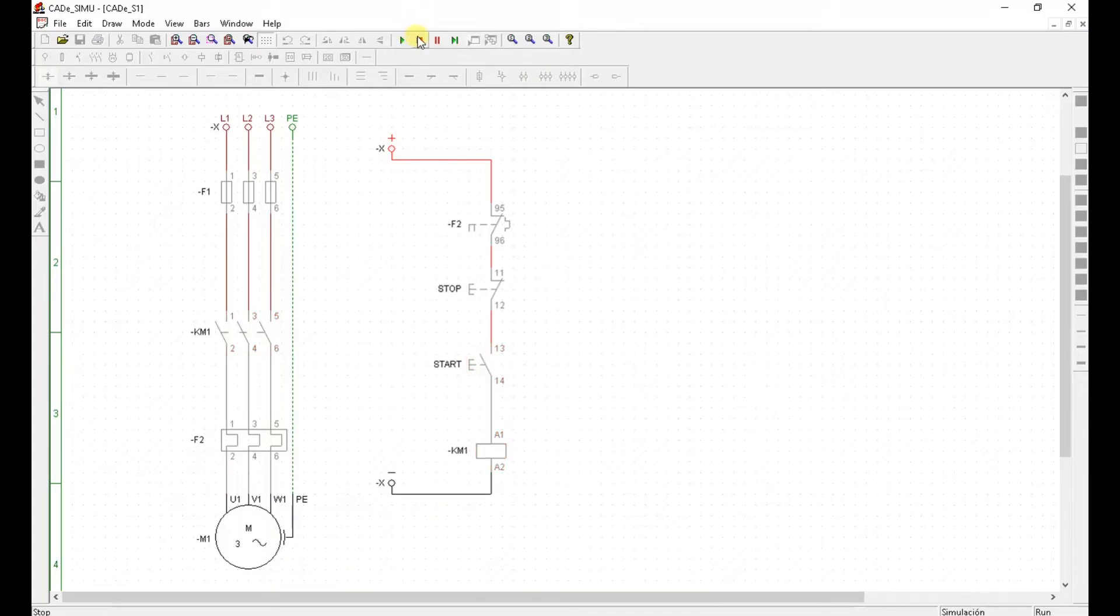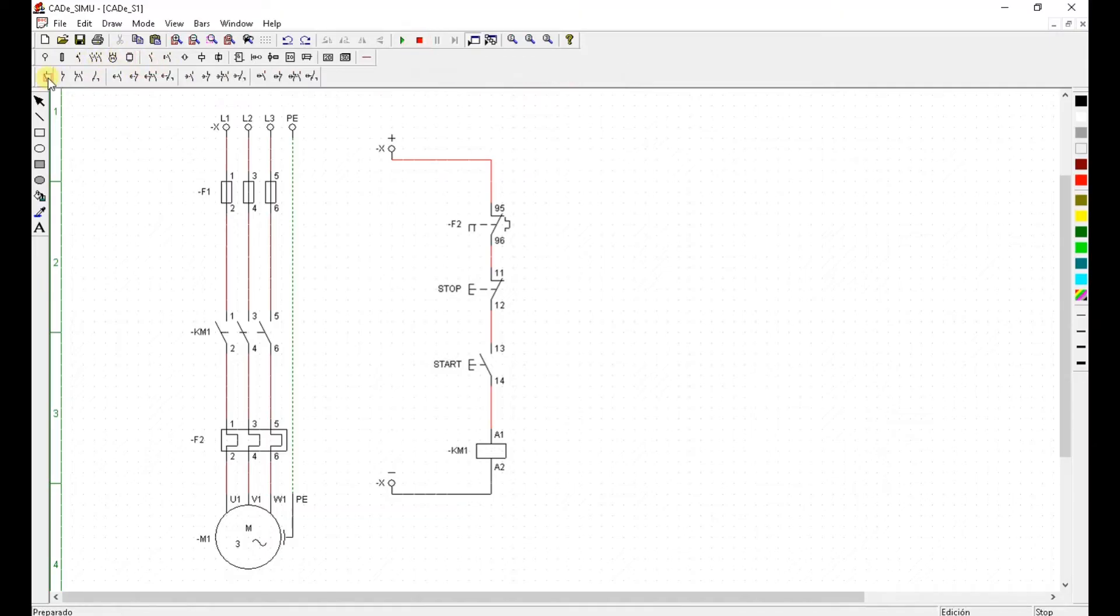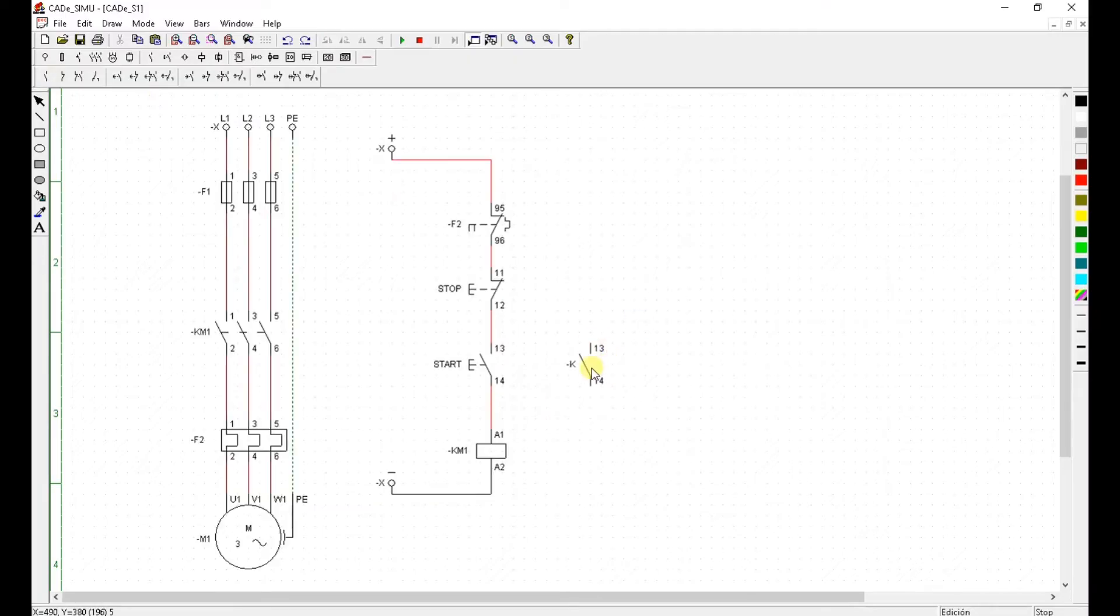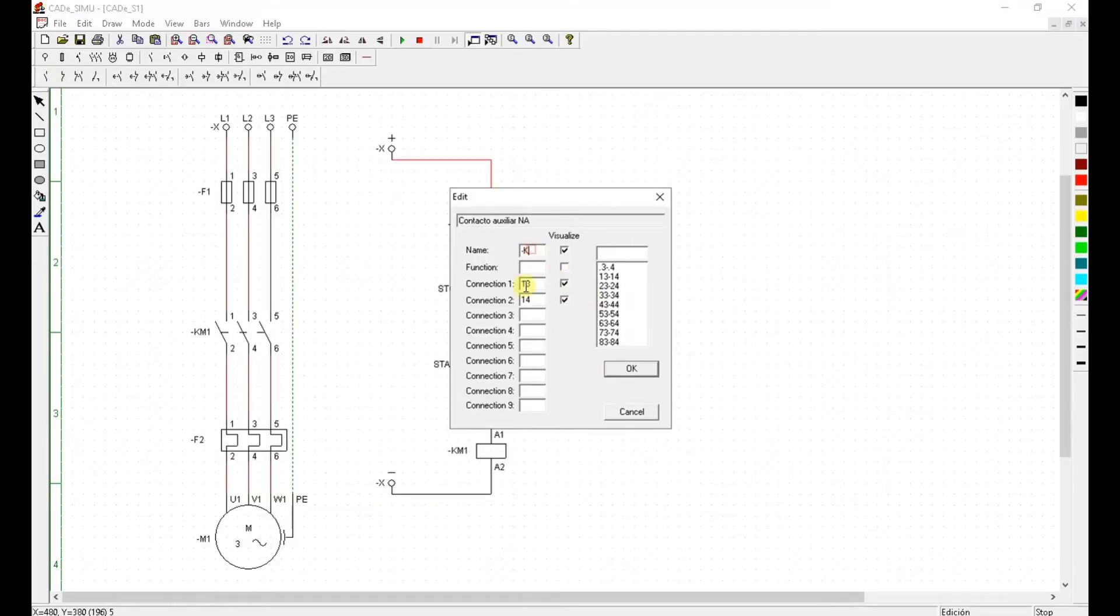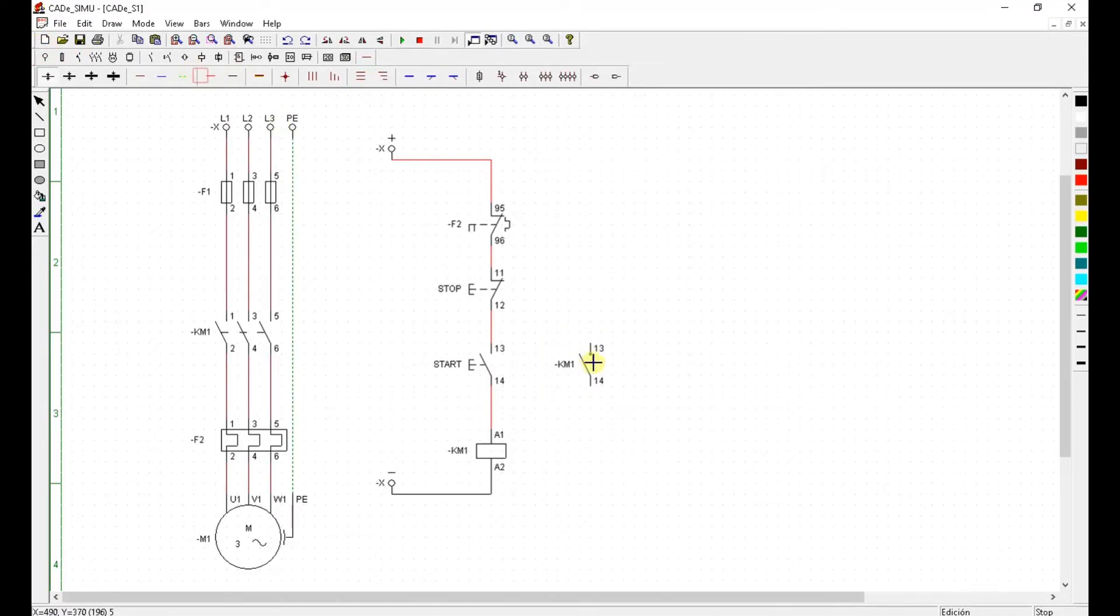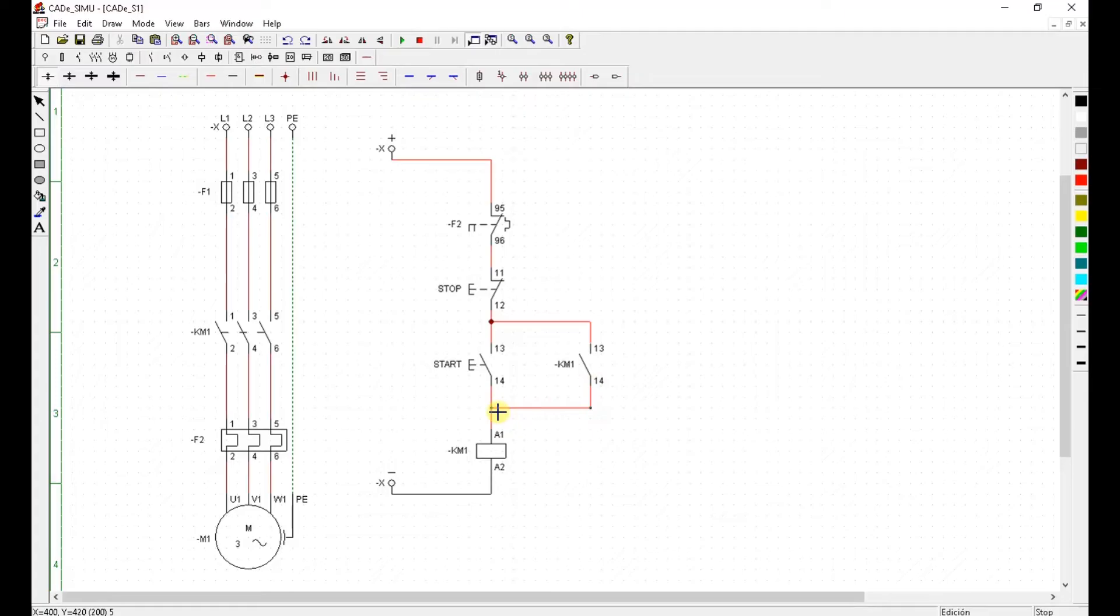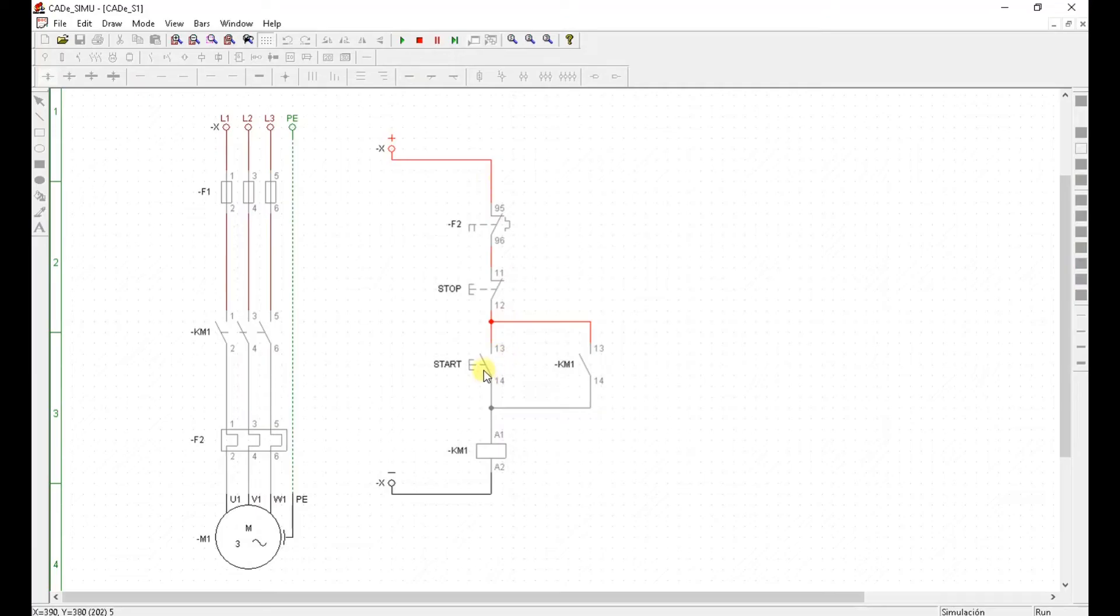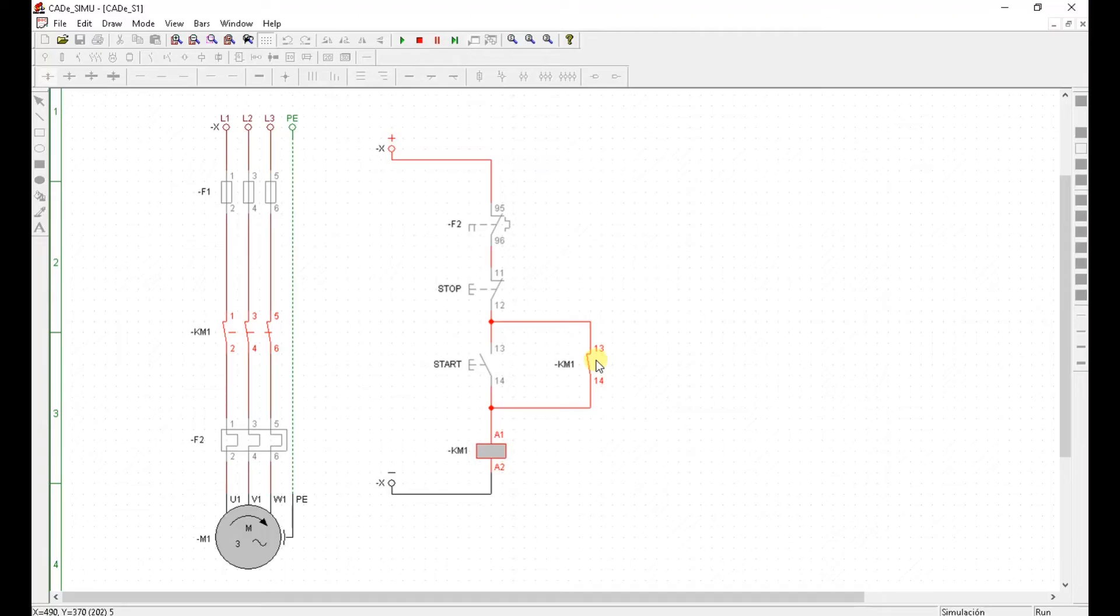We'll fix it by placing another normally open contact in parallel. And that contact comes off KM1. One end. OK. Let's have a look now. I'm pressing start. I'm releasing it. And the KM1 is still energized. That's because this contact. It's called retaining contact or latching contact.